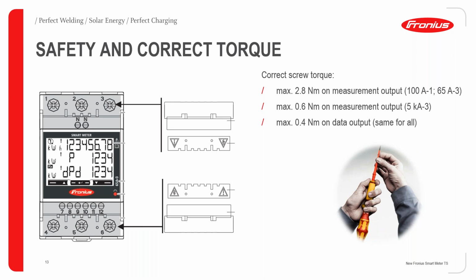If it is the 5KA3 smart meter, then the torque value is maximum 0.6 Newton meter. Because these cables are small, you are going to use them only for the voltage. There are no loads. This is not the actual phase you are measuring going through. It's only the voltage value you are going to measure here. So that's why this torque value is very, very less. So the cable will be smaller. And then if it is the data cable, then you have to use maximum 0.4 Newton meter only. This data cable is the same for all 3 types of the smart meter, like 100A1, 65A3 or 5KA3. They are all the same.